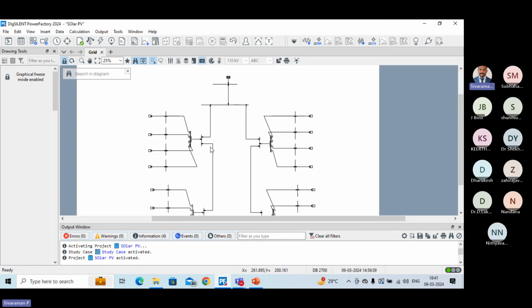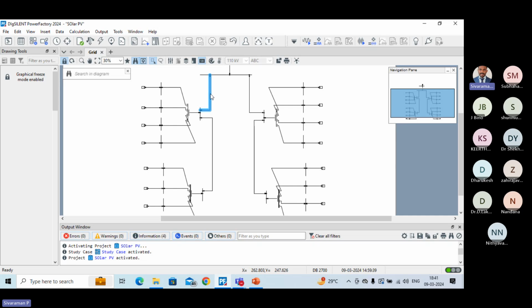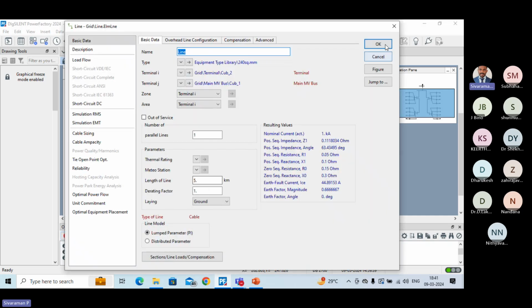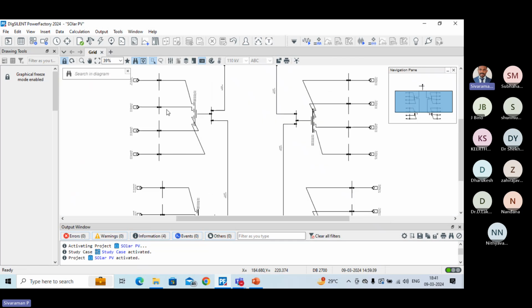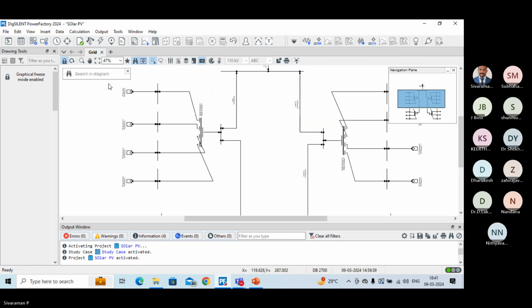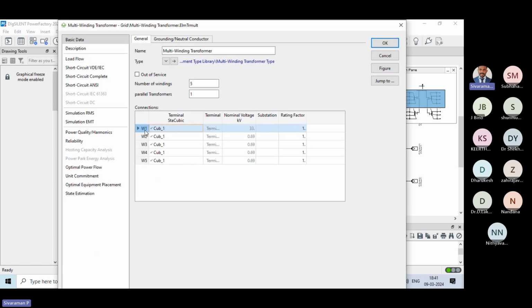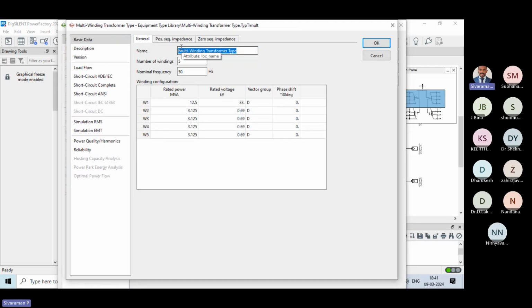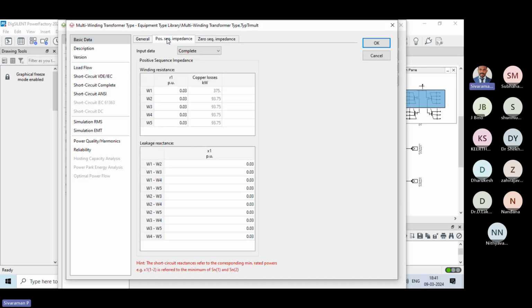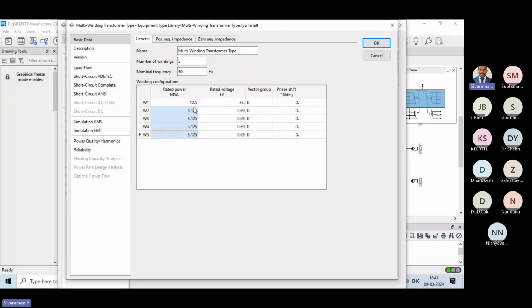This bus is the main medium voltage bus. From this bus comes the collector network I told you about. The collector network is this cable, 5 kilometer length. This cable goes to one inverter room, including the transformer. This is a 5-winding transformer, one primary winding and four LV windings. The primary winding is 33 kV and the four LV windings are 690 volt. Its power rating is 3.125 MVA each, so totally it is a 12.5 MVA transformer.